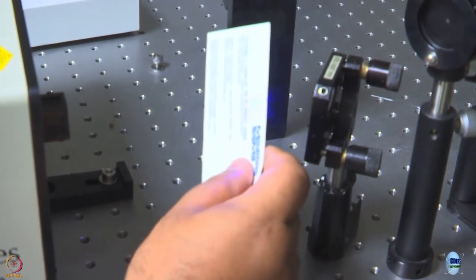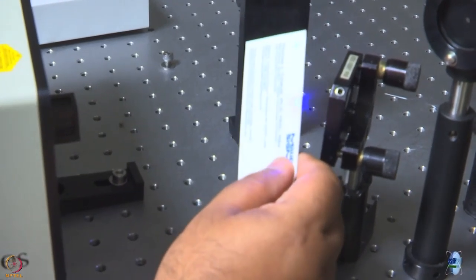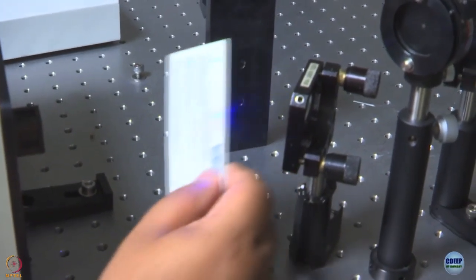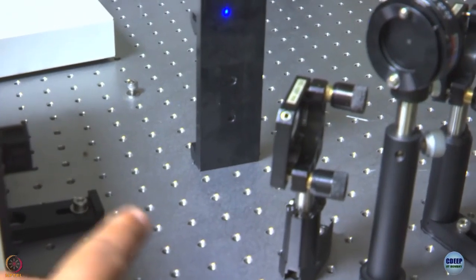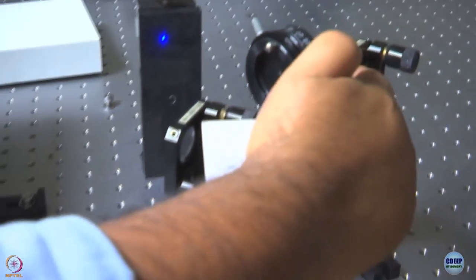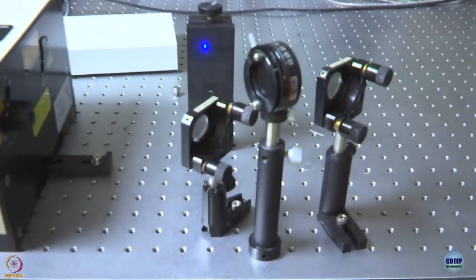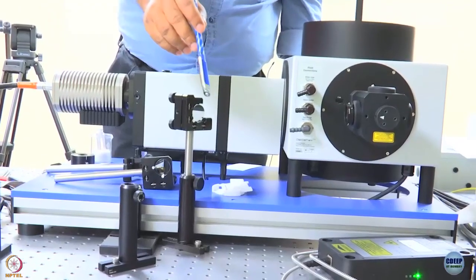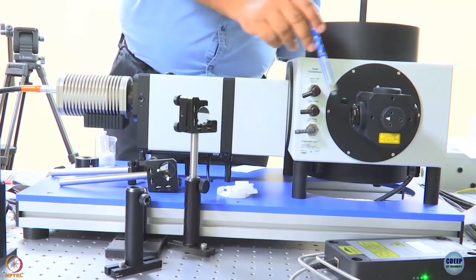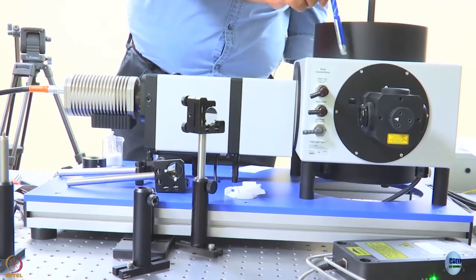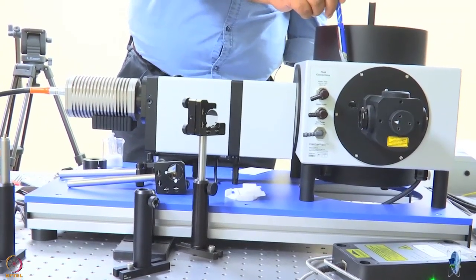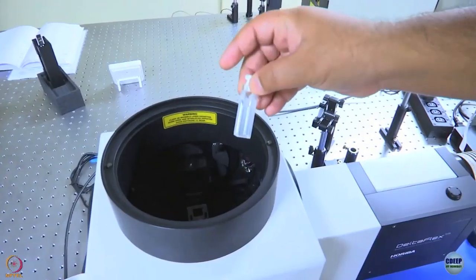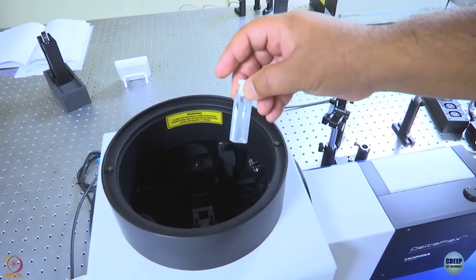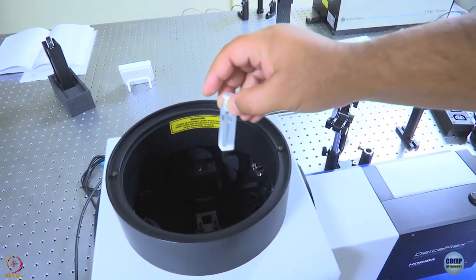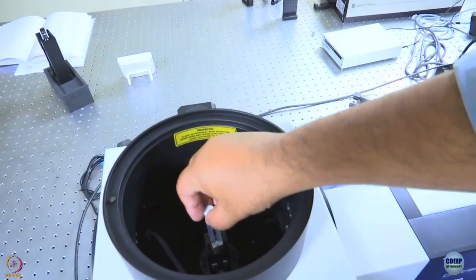Now, we have to choose which one we want, the blue one or the red one. Right now, the red one is being used. So, the red light goes, hits this mirror, then comes to this mirror and gets reflected into the sample chamber where we keep the sample. So, we have kept our sample in this cuvette, and that goes in here.